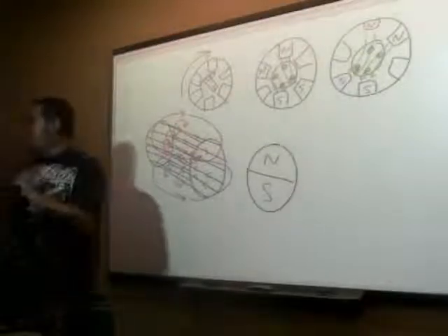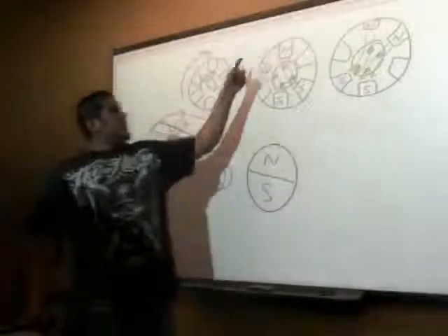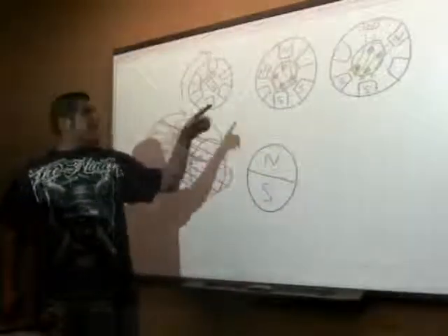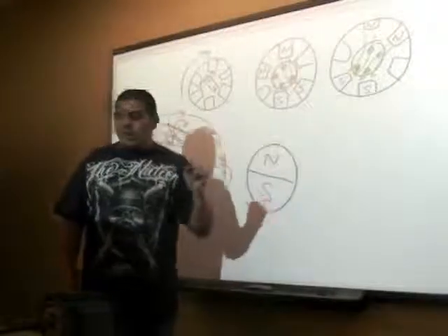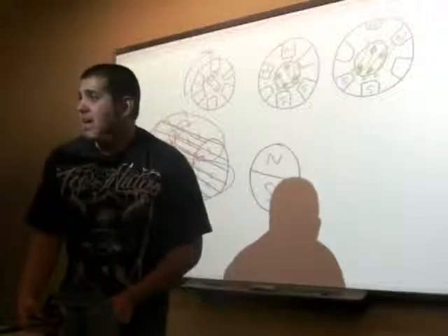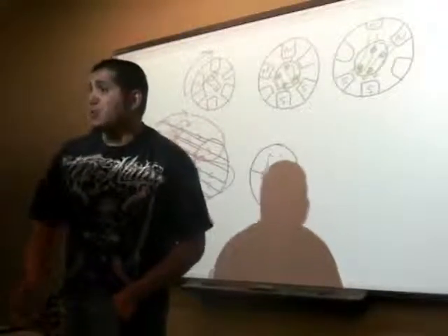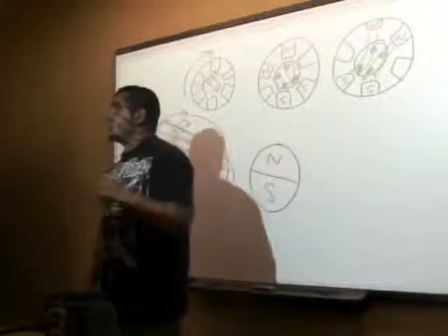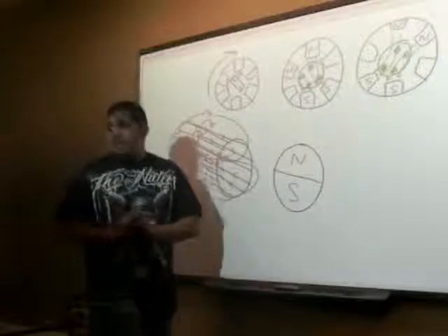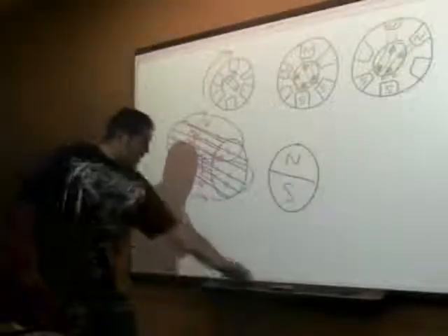Okay, now getting back to our speed, this thing is going 3,600 RPM. This rotor can't quite catch up. I mean, it's trying, right? And it's darn close. But it doesn't go the full speed of the rotating magnetic field. What that is called, it's called slip.